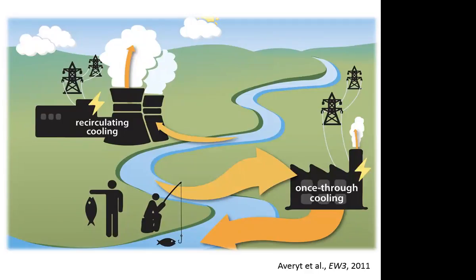An evaporatively cooled power plant will actually consume between 2 to 30 times more water than a once-through power plant per kilowatt, or per unit of electricity generated. So you have a larger consumptive footprint with evaporative cooling. On the other hand, a once-through cooling facility will withdraw upwards of 60 times more water per unit of electricity generated relative to a recirculating cooling plant - so there you have a larger withdrawal footprint.